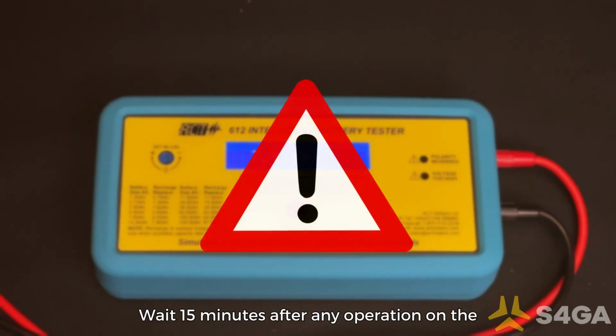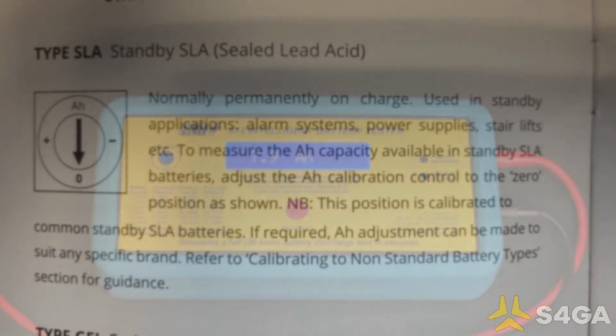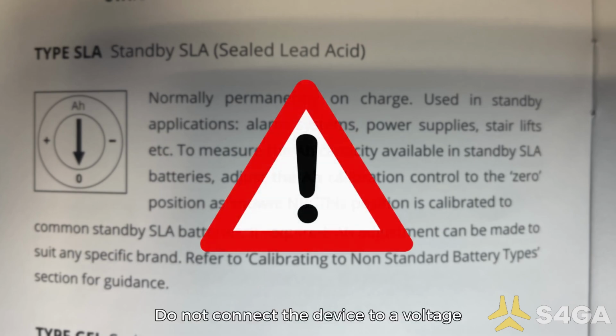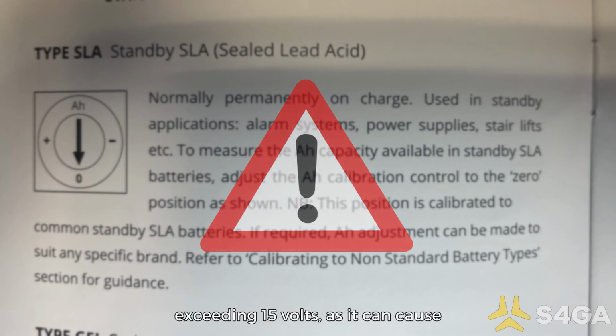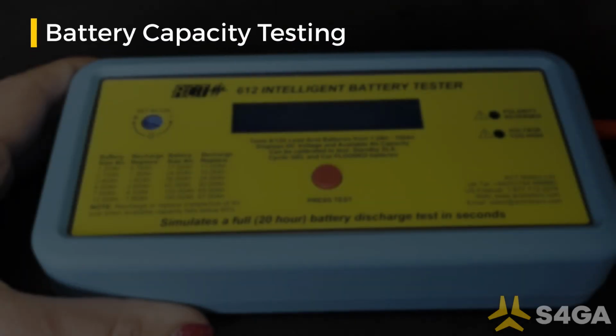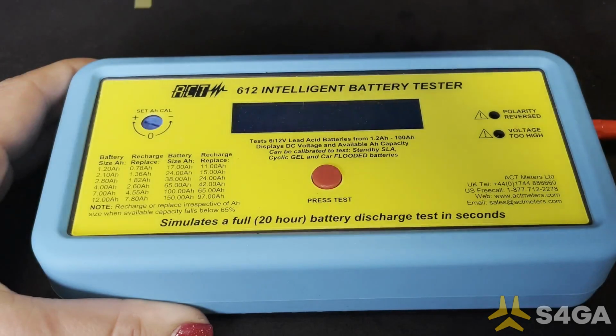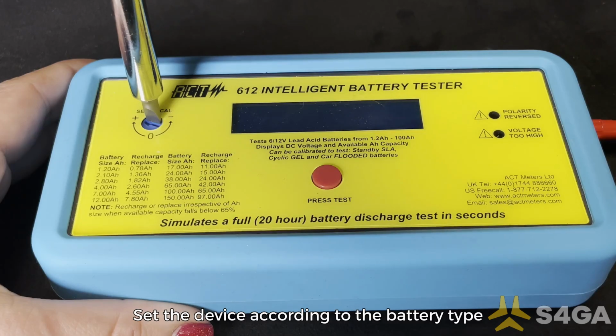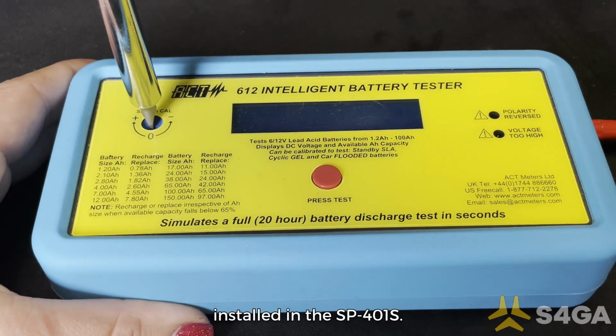Do not perform testing directly after charging or discharging the battery. Wait 15 minutes after any operation on the battery to allow the voltage to stabilize. This device does not support lithium-ion battery testing. Do not connect the device to a voltage exceeding 15 volts, as it can cause permanent damage. Set the device according to the battery type installed in the SP-401S.